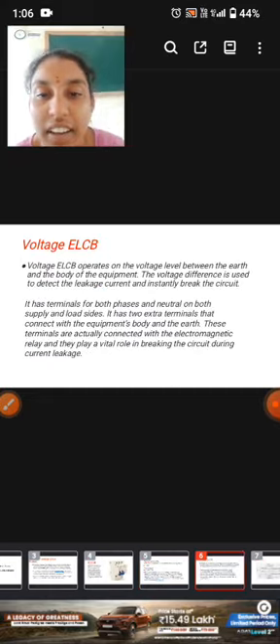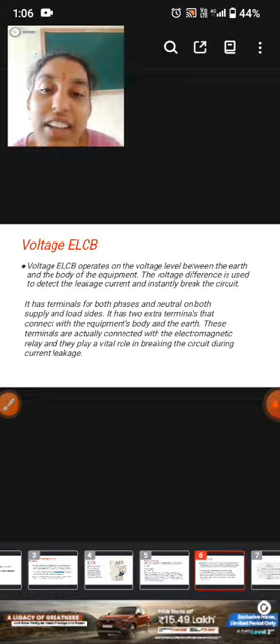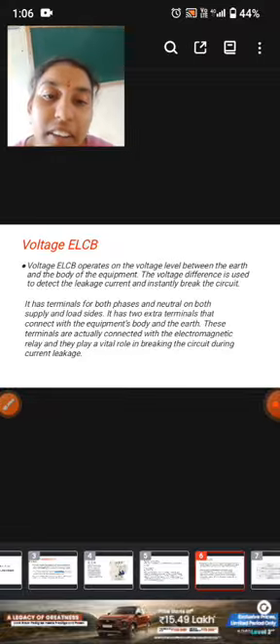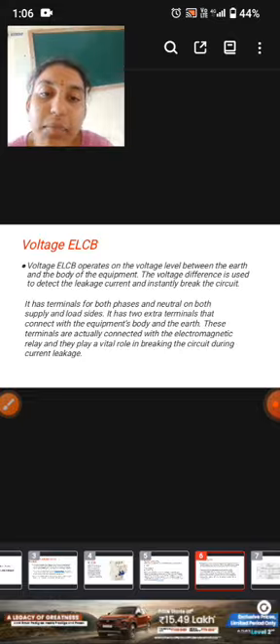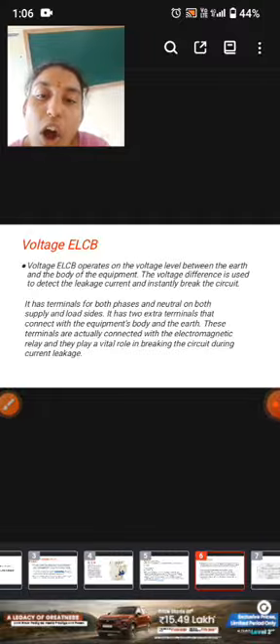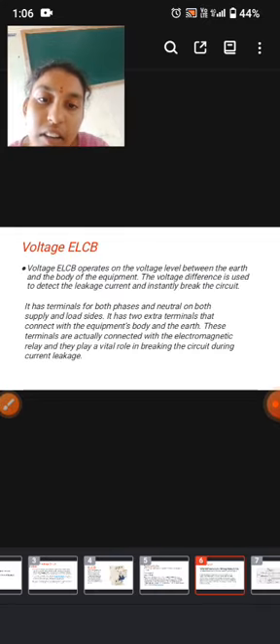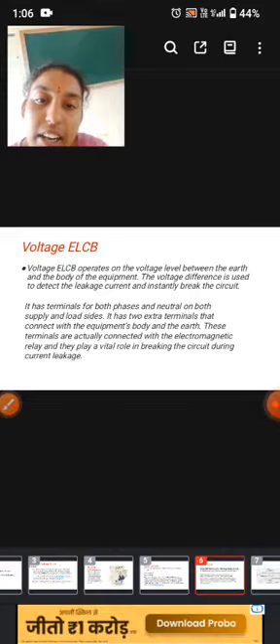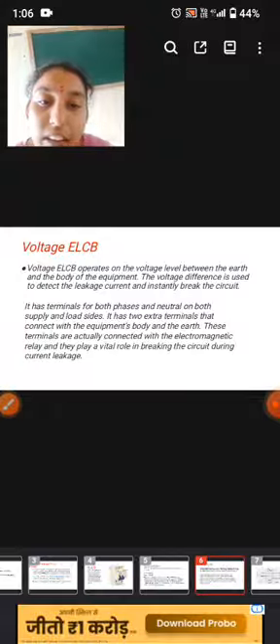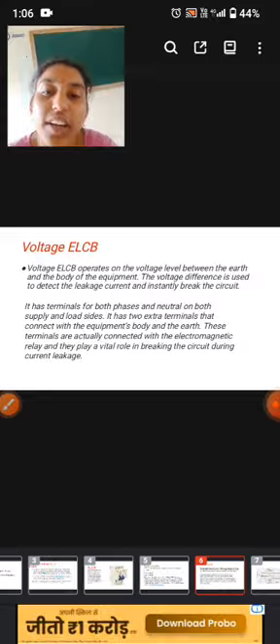Voltage ELCB. Voltage ELCB operates on the voltage level between the earth and the body of the equipment. The voltage difference is used to detect the leakage current and instantly break the circuit. It has two terminals for both phase and neutral on both supply and load sides. It has two extra terminals that connect with the equipment's body and earth. These terminals are connected with an electromagnetic relay and they play a vital role in breaking the circuit during leakage current.